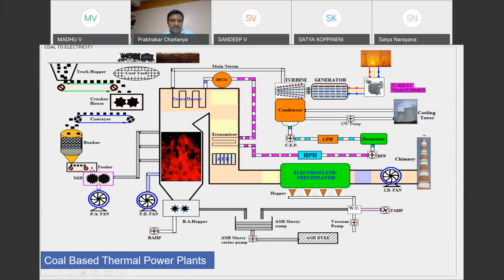So we get the fuel from the coal handling plant, and similarly we need to get the air. Through the FD fan, air is taken directly from the atmosphere and fed into the boiler, meeting the parameters required for boiler combustion: one is coal and the other is air, basically oxygen and the ignition temperature.